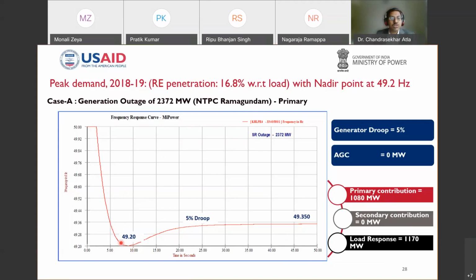Now, to bring the system down to 49.2, we have limited the primary response participation from the generation. For example, if you enable all the Southern Region generation to operate, the frequency will not come down to 49.2. It may go only to somewhere around 49.6 or 49.7. But if you limit the number of generators participating in the primary reserves, then you allow the frequency to go to 49.2. In that situation, the simulated frequency comes here, and the reserves required are around 1080 megawatt of primary reserves. If you restrict it, the frequency goes to 49.2. And during that condition, you can see the load response.